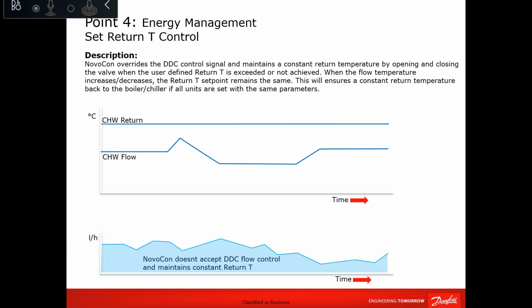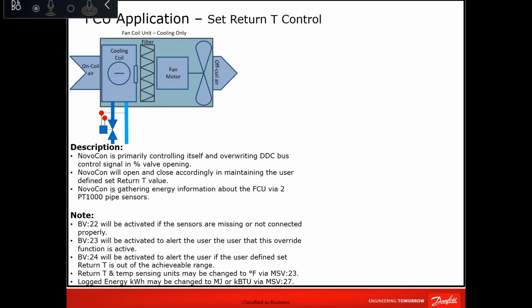Set return temperature. So we said one is minimum return temperature, one is set return temperature. The difference between minimum and set is that in case of minimum temperature control, the moment it achieves the temperature, it will release the control back to the local controller. If it is set temperature, it will only control based on the temperature. And as you can see here, the Novocon is primarily controlling itself and overriding the DDC BMS control signal in percentage of opening.